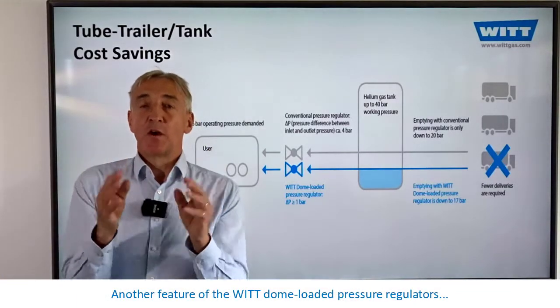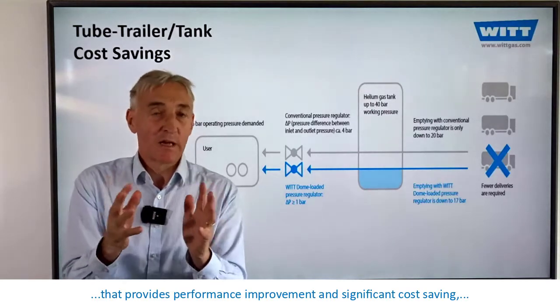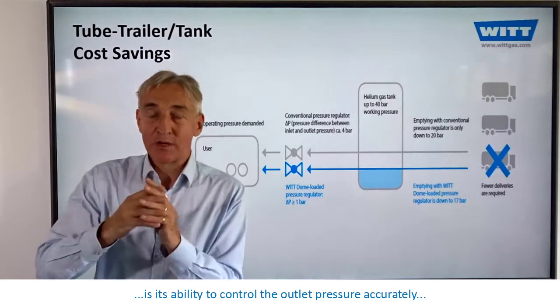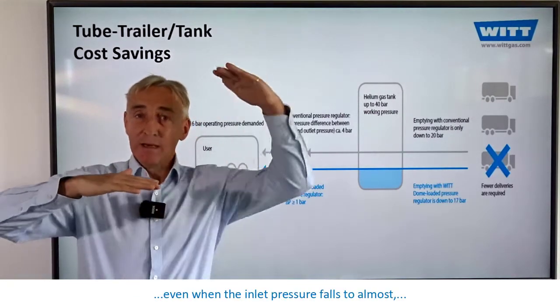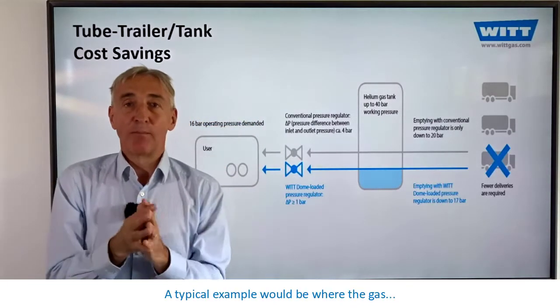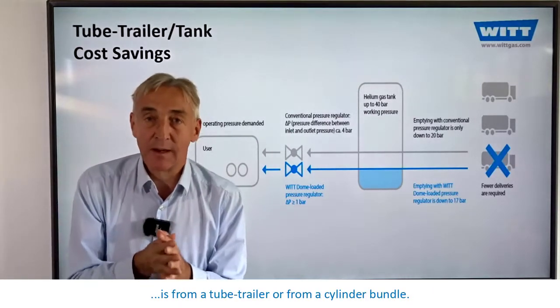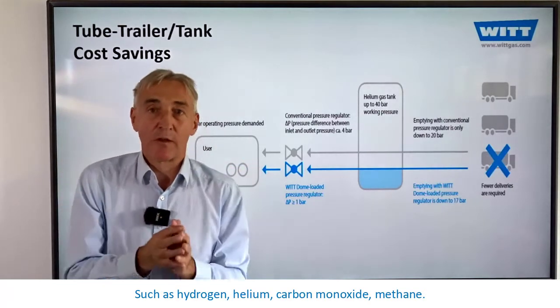A feature of the WITT dome-loaded pressure regulators that provides performance improvement and significant cost-saving is its ability to control the outlet pressure accurately and provide high flow when required, even when the inlet pressure falls to almost within one bar of the outlet pressure. A typical example would be where the gas is from a tube trailer or cylinder bundle, such as hydrogen, helium, carbon monoxide, or methane.